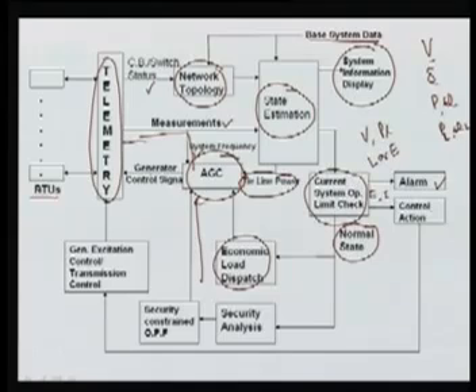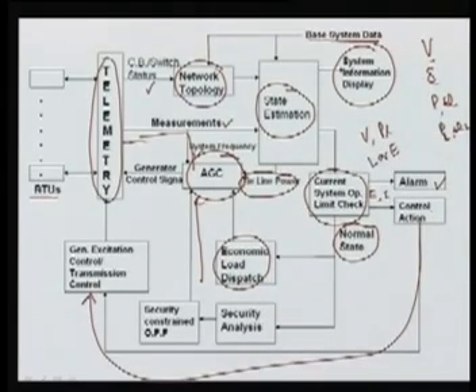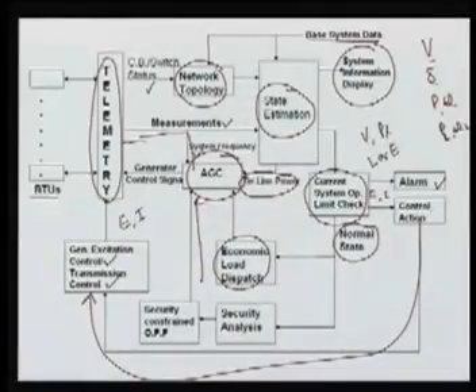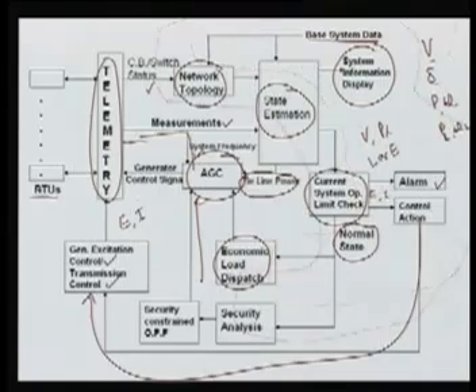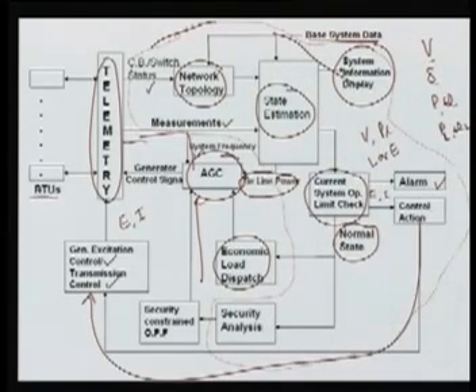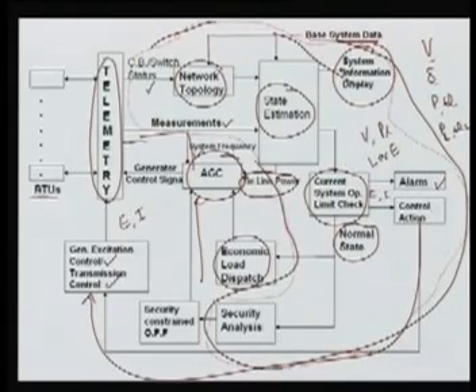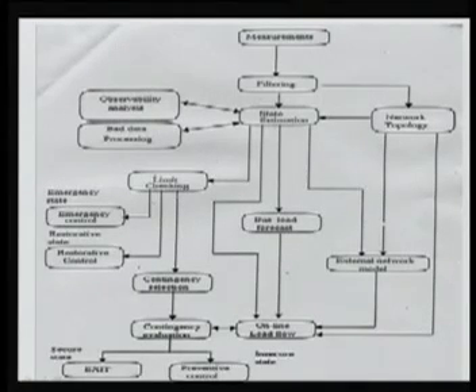Otherwise, if your system is not in the normal state, then there is no option. You have to directly apply the various controls to bring your system to the normal state. That is, we have to go for generation excitation control and transmission control, so that we can satisfy your equality and inequality constraints. That is how we bring our power system to the normal state. This whole process, if you see, which is with the red line here, is called the security monitoring and assessment function. Now you can see in detail what we do in the security monitoring and assessment functions of a modern energy management system.